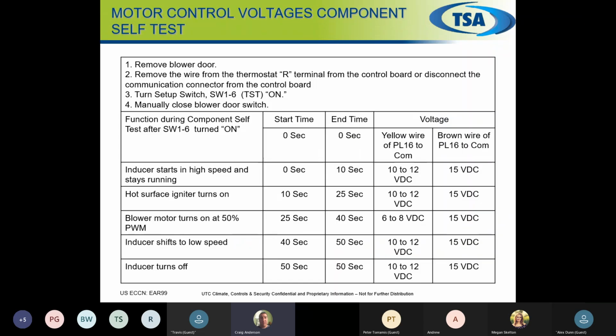So this is what we were looking at. Our brown wire, constant, 15 volts DC, in that range. Like we said, your meter will be a little bit different. Yellow wire from that motor, 10 to 12 volts DC, constant, steady. The only time it changes is when that motor turns on. Once that motor turns off, that voltage should change back to 10 to 12 volts DC. At any point, if you're getting 0 on your brown or your yellow, remember, brown's talking, yellow is coming back. So anything below 10 volts DC, then we're looking at the problem of where it's generated, whether it's the board or the motor.